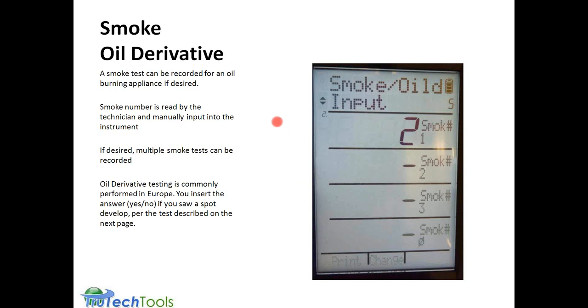All right. Smoke or oil derivative. A smoke test, again, can be recorded in this screen, but it's done through another device, either a manual smoke tester or a digital smoke tester. It can be recorded on this screen. Then an average will be developed. You could print it out from the screen or store it to be printed with your whole combustion test. You can do multiple tests, up to three, and it will give you an average. And this oil derivative is commonly used in testing in Europe. And you simply insert an answer, yes or no, if you saw a spot develop. Basically, it looks for raw fuel being blown through the system. It's not a test that's done in North America that we're aware of.